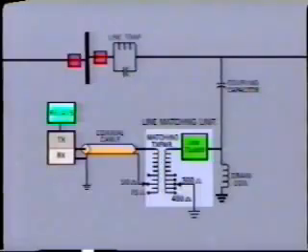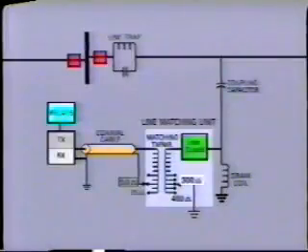The LMU taps should initially be set as near as possible to the anticipated value of line impedance, usually about 300 to 400 ohms, and the impedance of the coaxial cable usually 50 to 75 ohms.